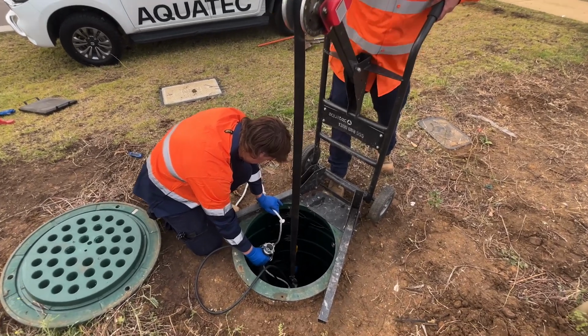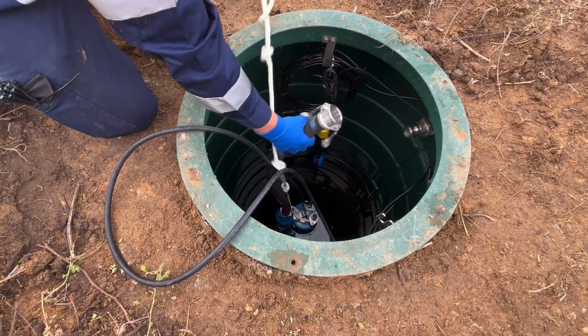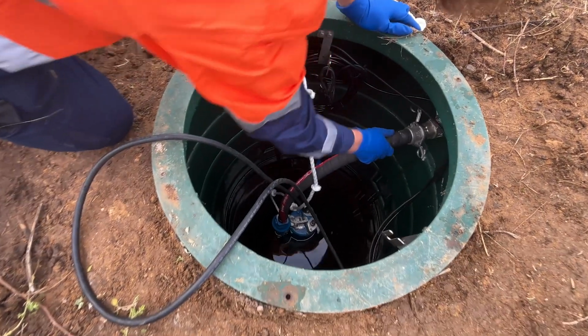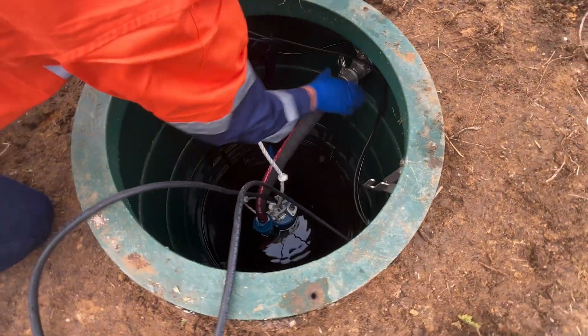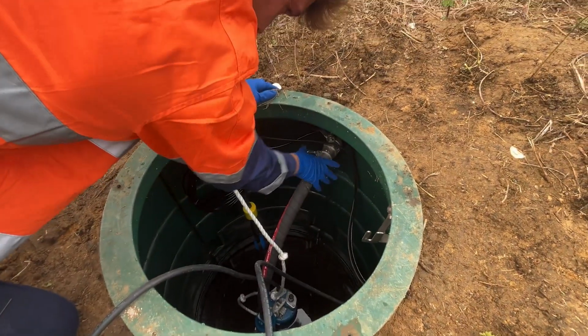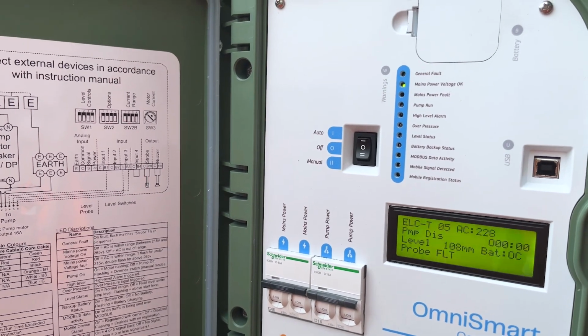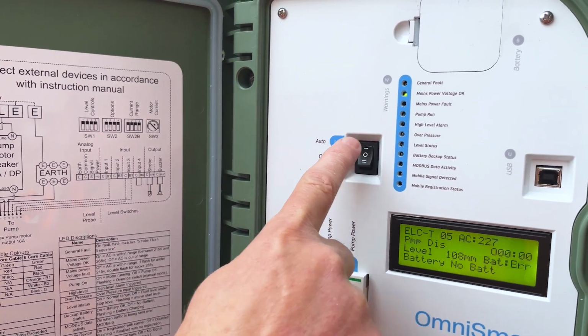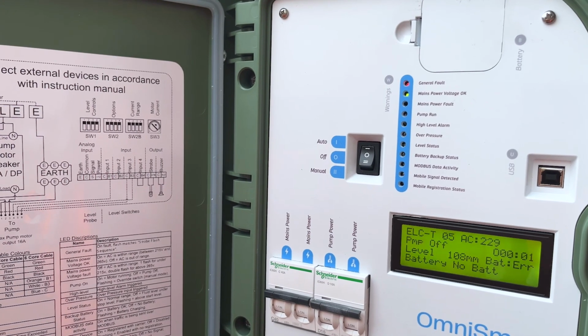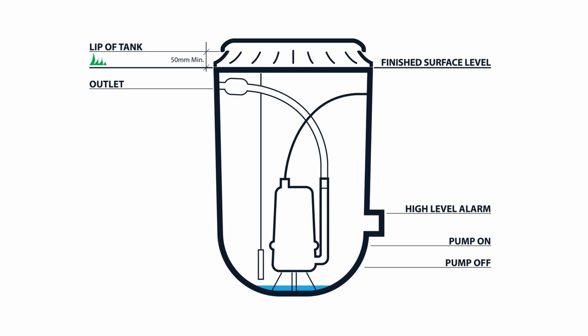Lower the pump back into the well and connect the outlet via the cam lock. For a pump using the guide rail system, ensure the pump seats correctly. Let's begin the testing phase: turn the control panel on and put everything into auto. Ensure that all the startup delays are complete or bypassed for the purpose of commissioning.